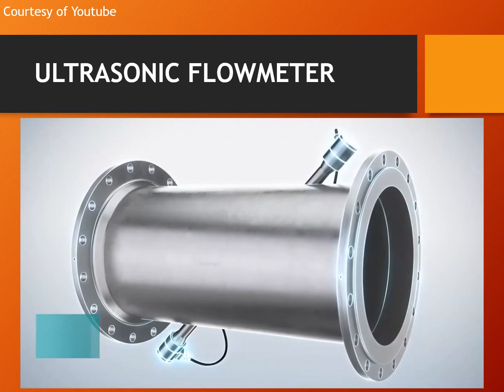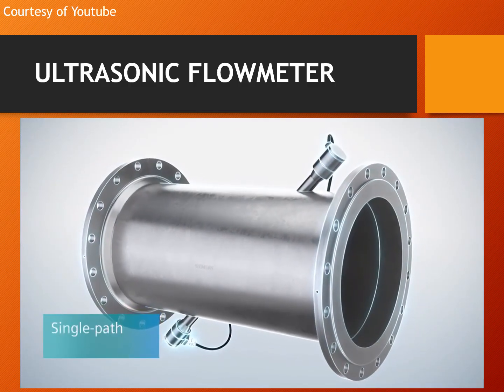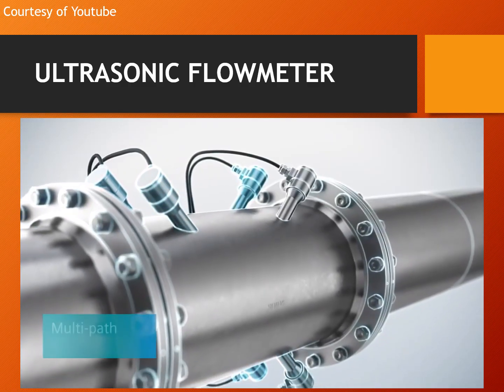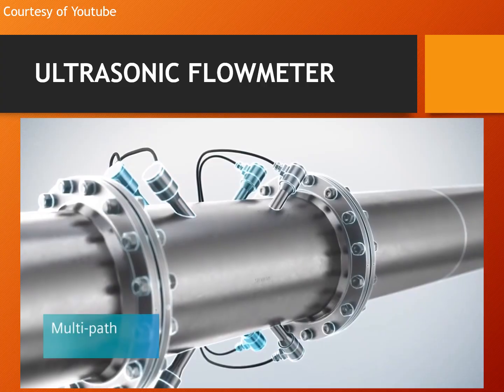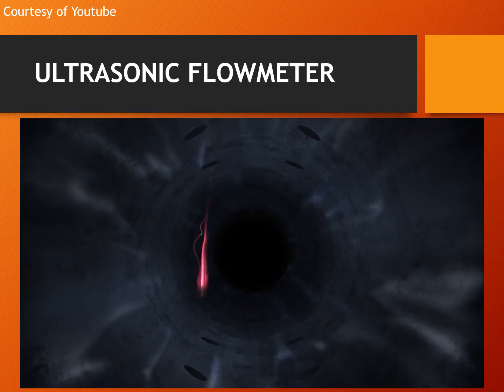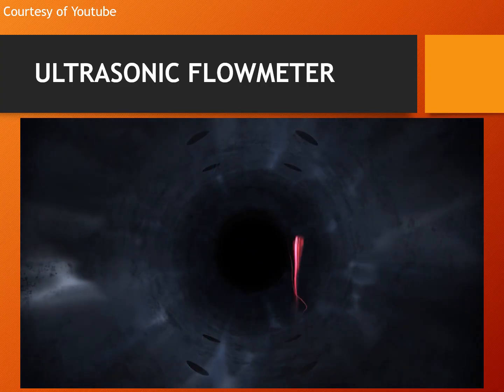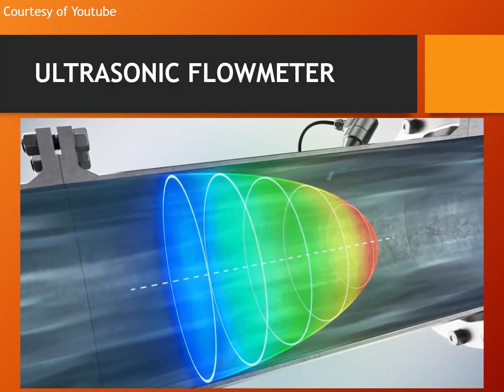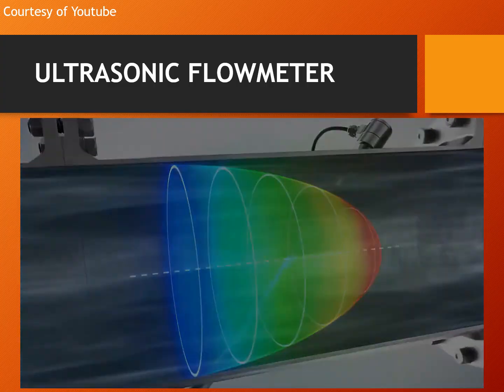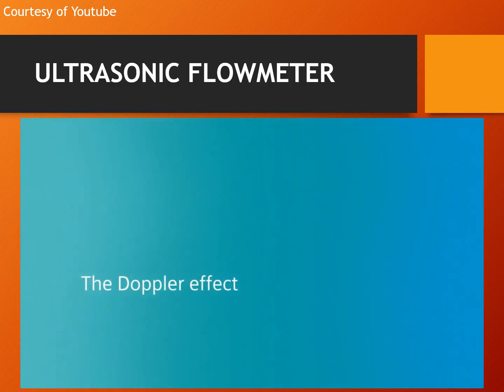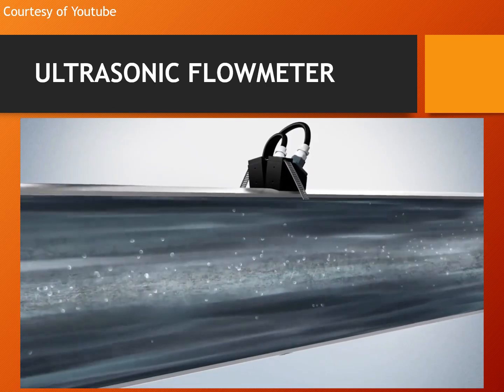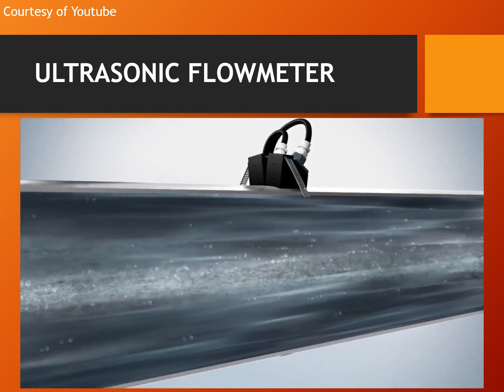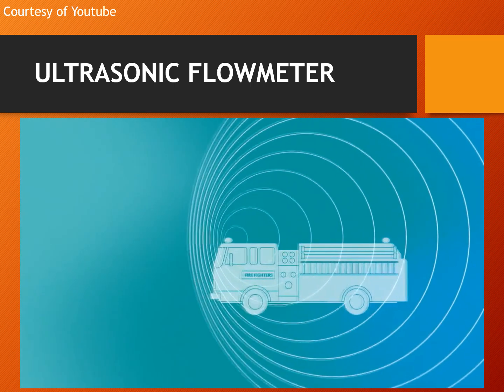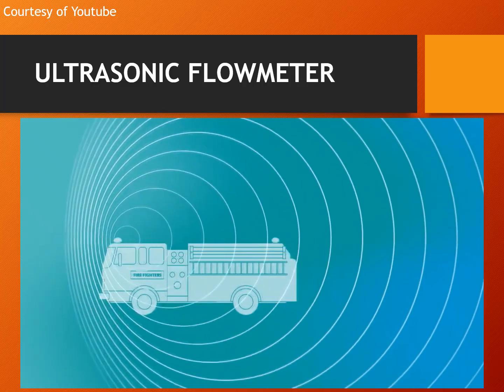Siemens offers a wide range of solutions, from single-path transit time to highly complex multi-path measurements used in demanding applications where performance may be affected by flow profile distortion. If the medium contains dispersed particles or bubbles, Siemens uses a method based on the Doppler effect, a frequency shift similar to a passing fire engine.